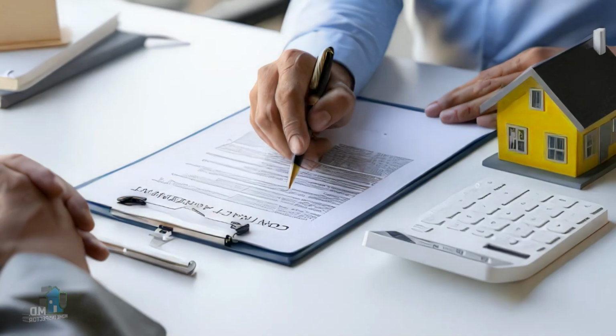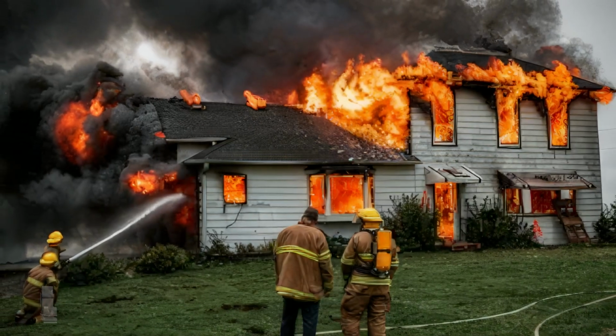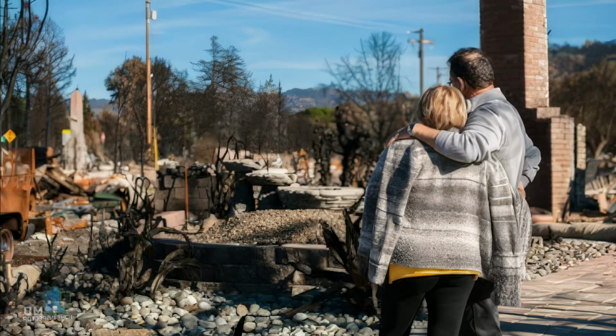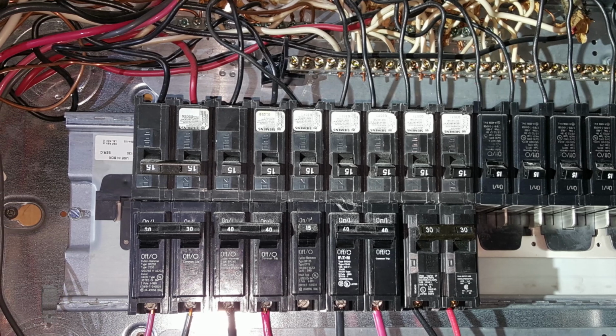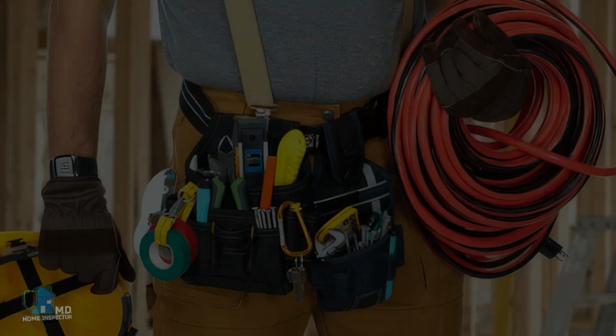This brings us to the next point, liability. If you have a fire in the house and the source was electrical, the insurance company will see the wrong branded breakers in the panel, and there's a chance that they will use that against the owner. So why take that chance? Finally, many of the conditions inspectors report on are based on not being best practice, and wrong branded breakers in a panel is not best practice. It's a condition that should be reported on, as even though it may have been working perfectly for years, I think the homeowner should be aware of this potential danger in the house.